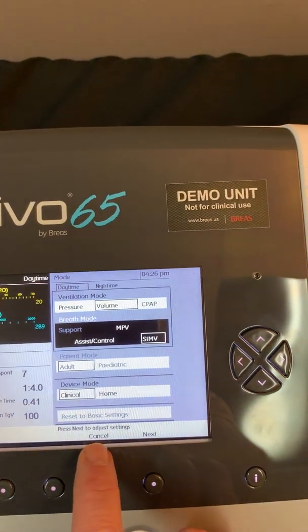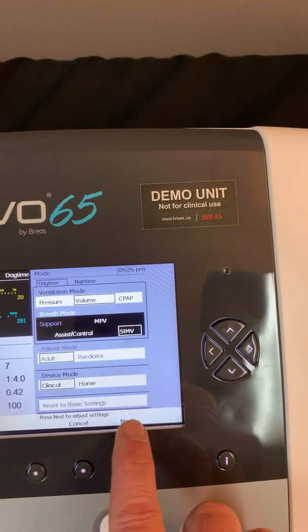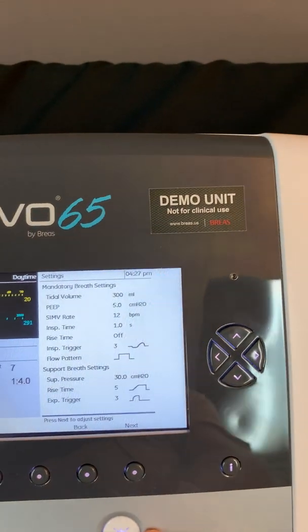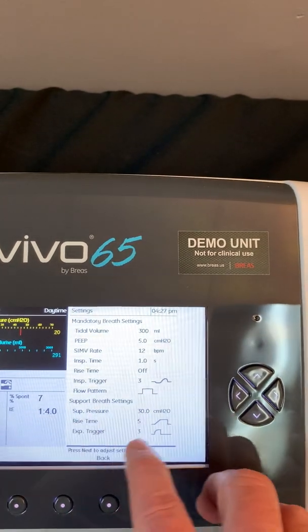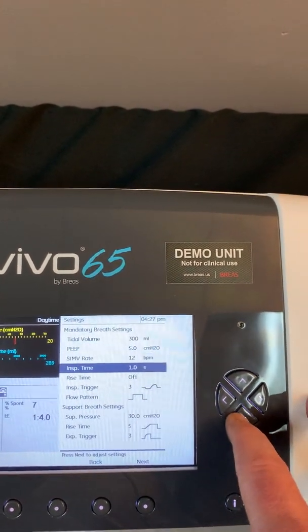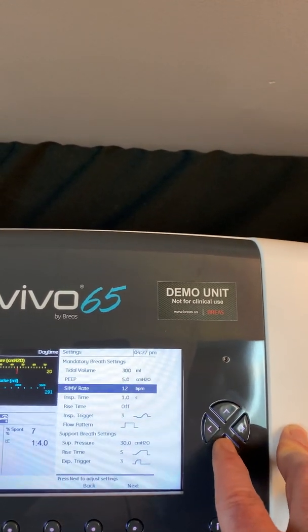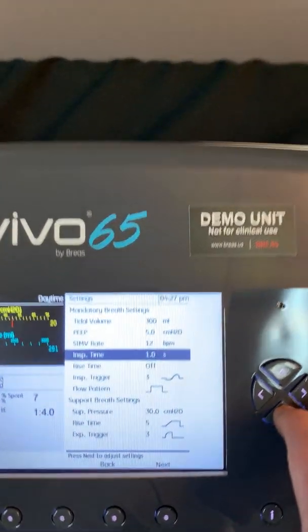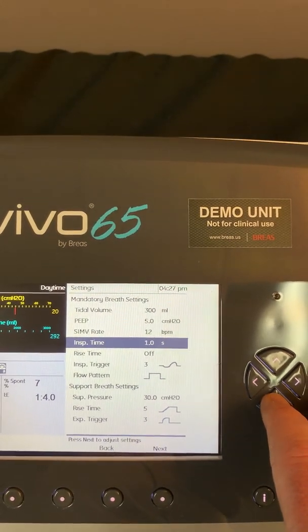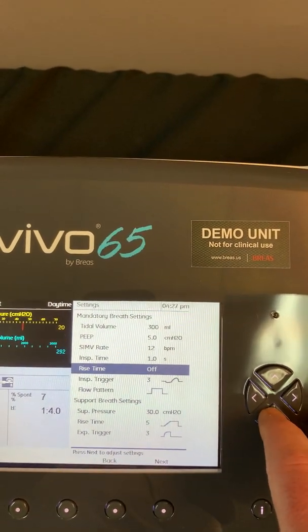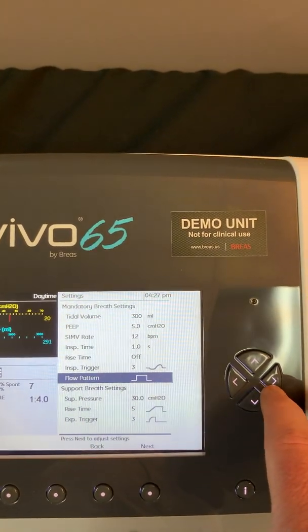Down here you'll see a cancel button to cancel out of making a mode change, or a next option. I'm going to press the next button, which is now taking me to my settings. All of my settings are on one screen. Navigation through this menu is exactly the same as the mode menu — up and down to highlight, left and right to change. I currently have a tidal volume of 300, a PEEP of 5, a set SIMV rate of 12, inspiratory time of 1, rise time is turned off currently, inspiratory trigger of 3, and a flow pattern of a square waveform.